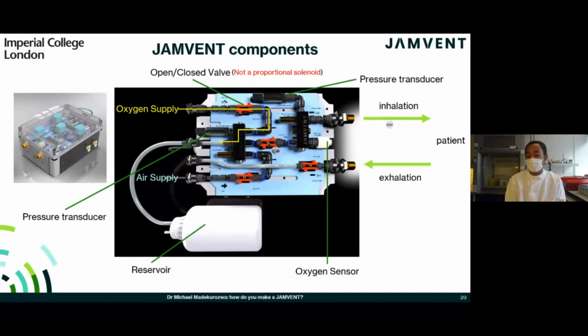Firstly, as a clinical output, so the clinician can see what's going on in the lung in terms of pressures. And secondly, as a safety mechanism. If the pressure in the lung goes too high, the system will detect it and act accordingly to decrease it. Lastly, the system has pressure release valves here and here, which limit the pressure that the system can actually get up to. These types of safety mechanisms are typical of ventilators because, as was mentioned by Dr. Mathiszig-Lee, ventilators ventilate lungs, and lungs are very, very delicate organs. So ventilators have to have several safety features to prevent them from damaging the lungs.